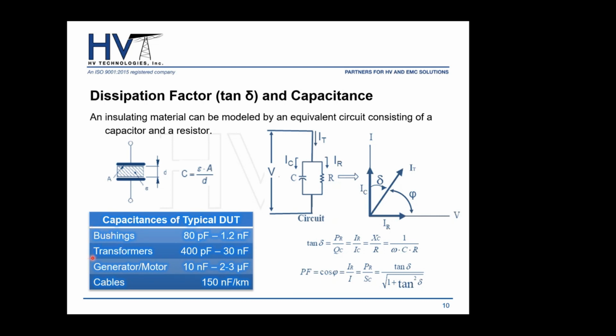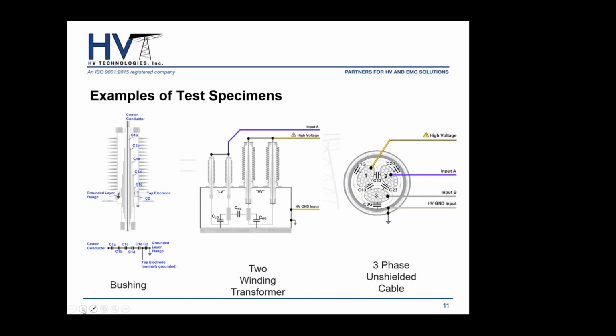Then when we get to generators and motors, it gets a little bit more complicated because the capacitance values are a bit higher. A generator, motor, or rotating machine will have anywhere between 10 nanofarads and 2 to 3 microfarads. And then, of course, we can also test cables, which have a rule of thumb capacitance of 150 nanofarads per kilometer. So we've been talking about transformers, bushings, and now cables, and we're talking about capacitance. We have to understand how these capacitances in these different devices or components, or what we call specimens, are modeled.